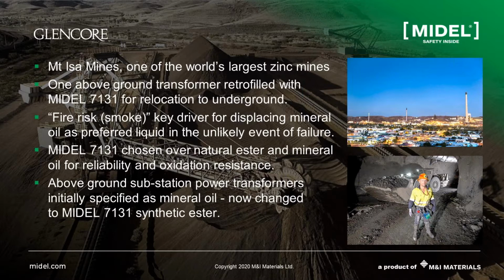Distribution transformers that were originally above ground were to be relocated underground. The electrical superintendents were very concerned about the risk of fire and then smoke in a confined space. This would make a safe evacuation of people almost impossible. To mitigate both concerns, the transformers were retrofilled with MIDEL. Recognizing the benefit in their existing fleet, the operator then acted quickly to change the specification of a new substation from mineral oil to MIDEL.